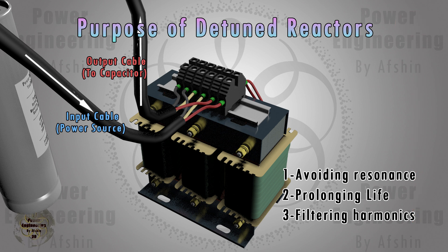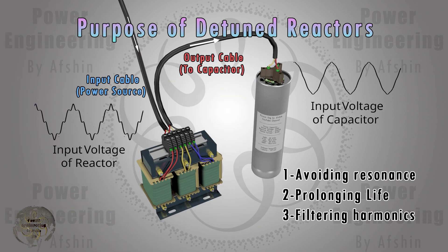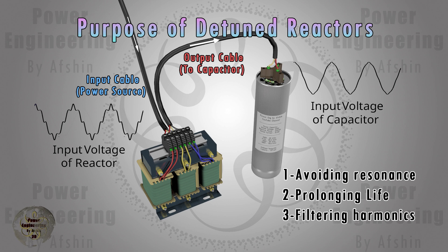By avoiding resonance, detuned reactors protect capacitor banks from being exposed to high harmonic currents, which can lead to overheating, reduced lifespan, and potential failure of the capacitors. While detuned reactors are not primarily designed to filter harmonics, they can reduce the flow of harmonic currents through the capacitor banks, contributing to overall harmonic mitigation in the system.